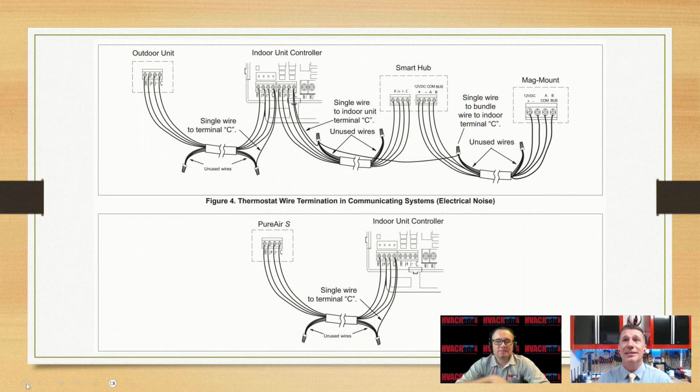All right. Let's start at the indoor unit, Todd. All right, let's go to the indoor unit. Interesting that everything's tied back to the indoor unit on these unitary. Yeah, it'll be completely opposite when we get to our ductless. Absolutely. But all of our unitary, our primary DC voltage is coming from that indoor control board. Yes. So let's look at this indoor control board.